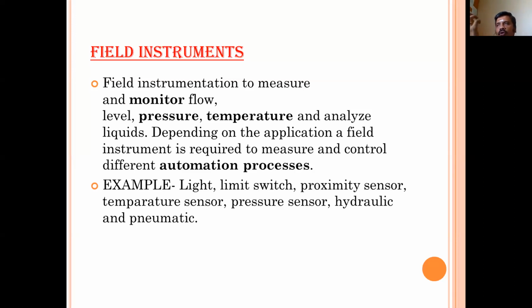So what is a field instrument? You need some instruments to measure the process. It can be a flow process, a level process, a temperature process, or a pressure process. Suppose you have a tank, and you have to maintain the level of the tank at a particular level. There you have to place a smart sensor. The transmitter, the field instrument, will get the level data and transmit the information to the PLC or DCS. So field instruments are nothing but data gathering devices, sensors and actuators. It can be a sensor or it can be an actuator.